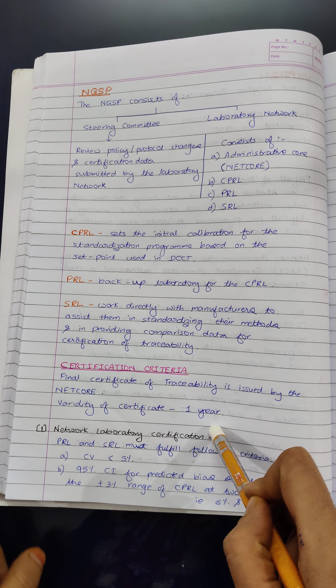So the validity of the certificate is 1 year. There are 3 types of certification provided by the NGSP. First one is network laboratory certification. The PRL, primary reference laboratory, and SRL, secondary reference laboratory, must fulfill the following criteria. The CV or coefficient of variance should be less than 3%. The 95% confidence interval for predicted bias should overlap the plus minus 3% range of CPRL at the 2 HbA1c concentrations, that is 6% and 9%. The PRL and SRL should fulfill these 2 criteria to get the network laboratory certification.